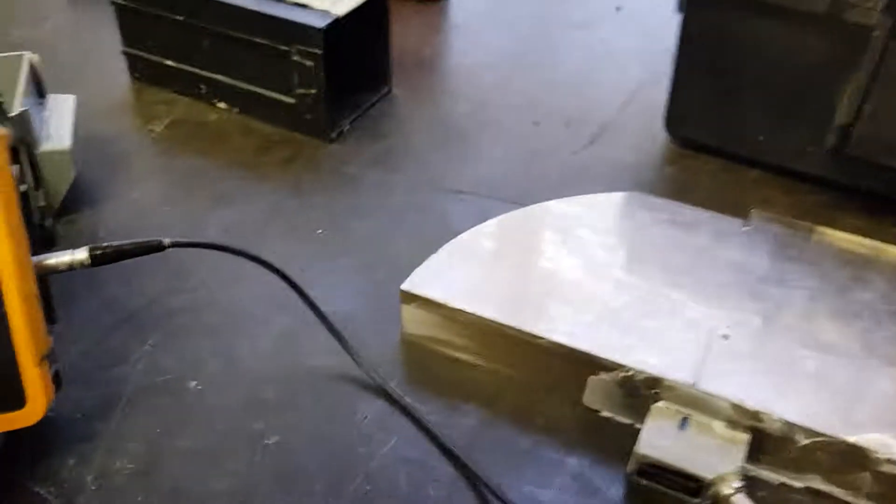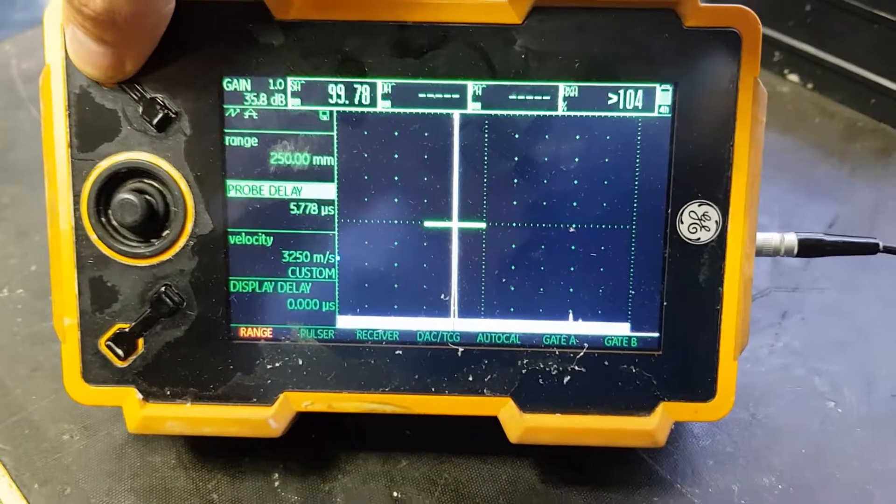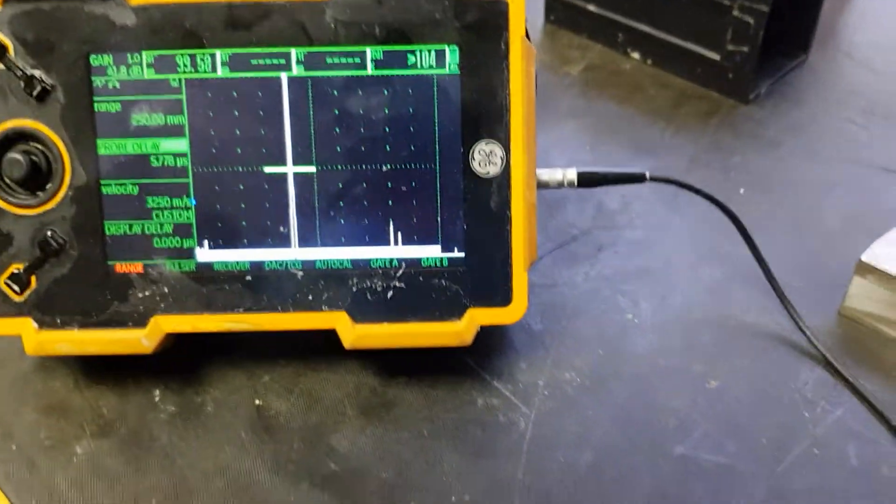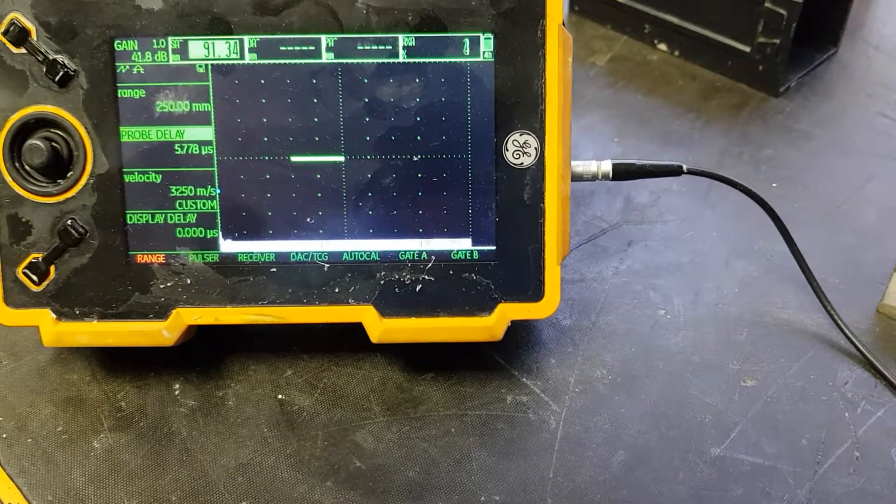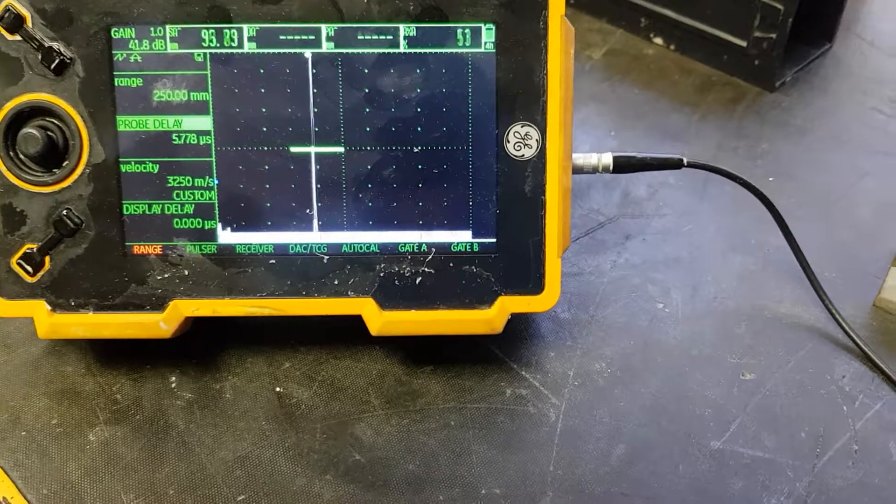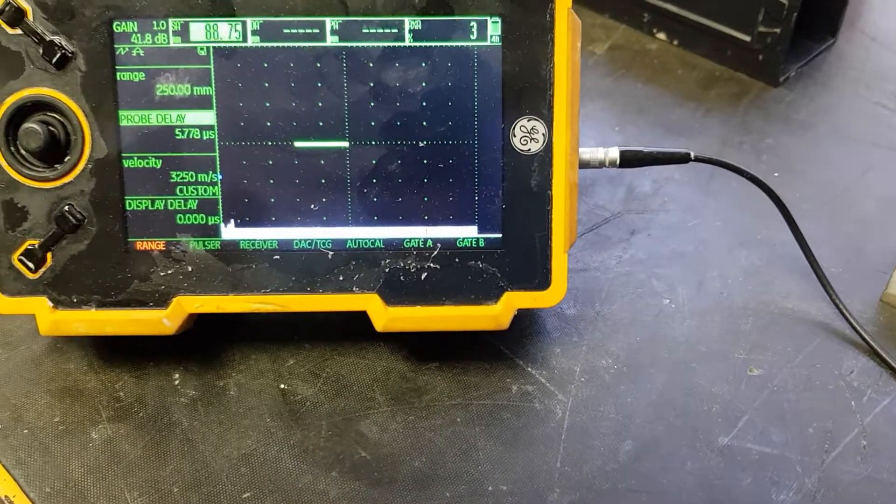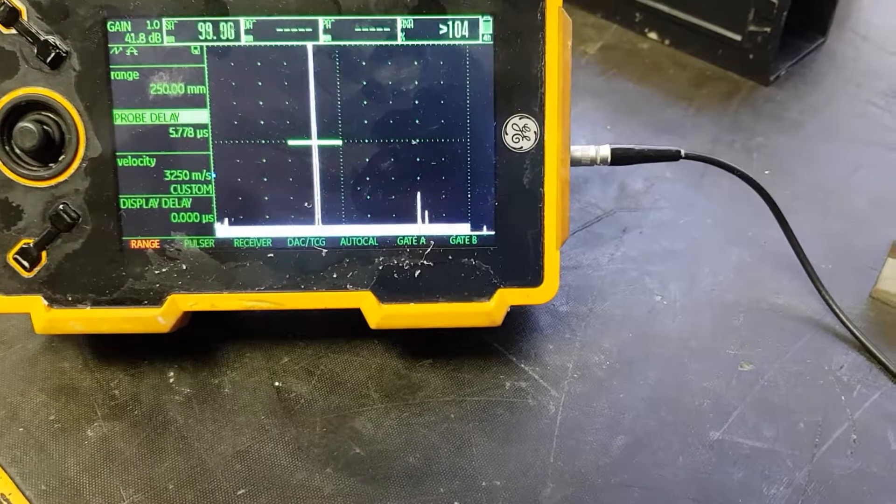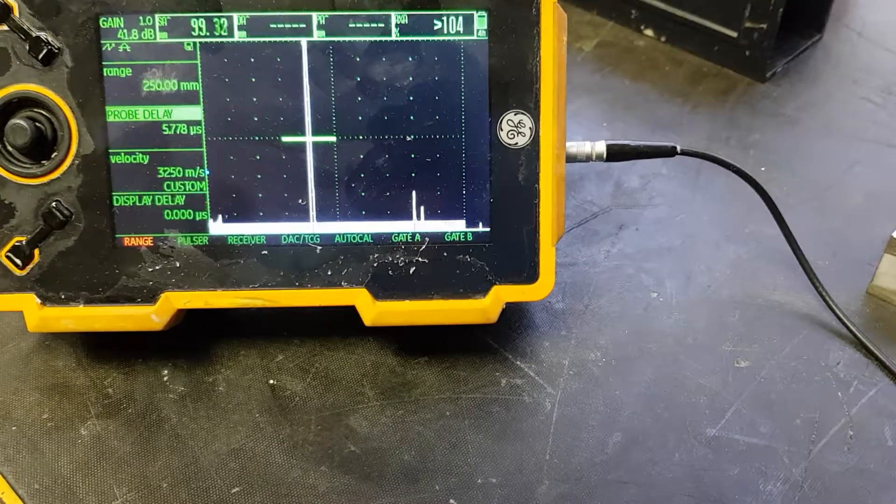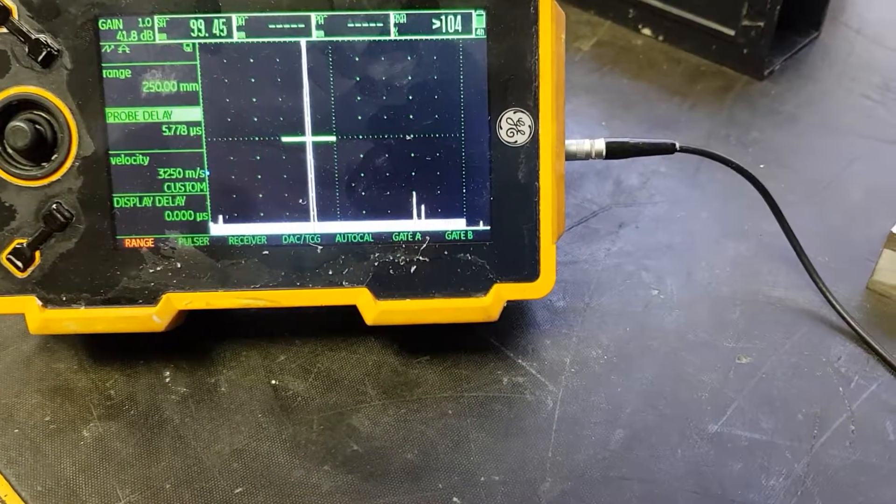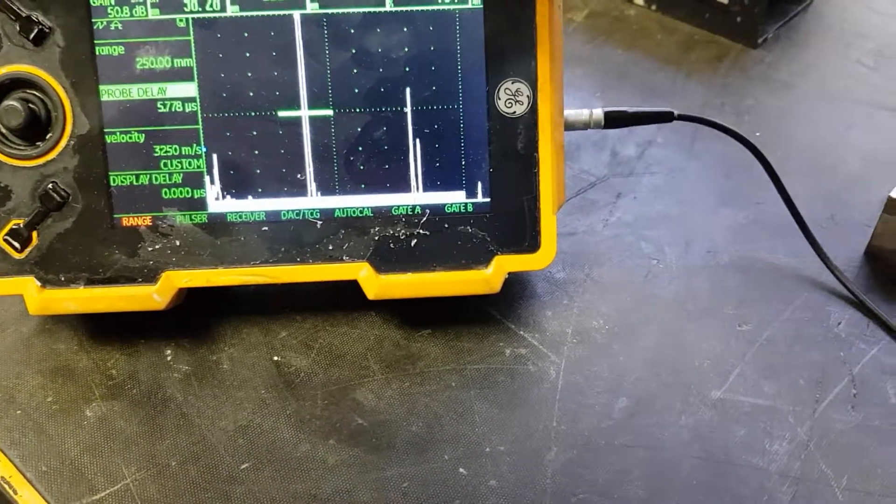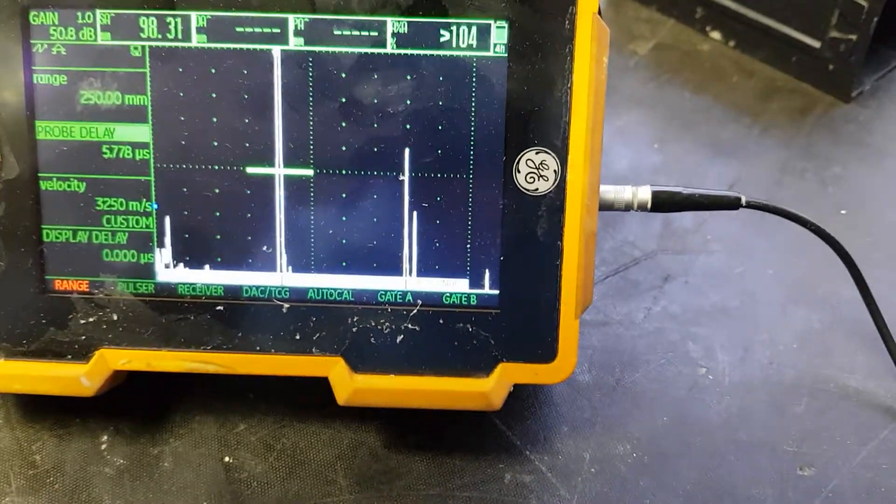If we increase the gain, we should also see the repeat echo pop up there. The process is almost the same as with the zero degree probe.